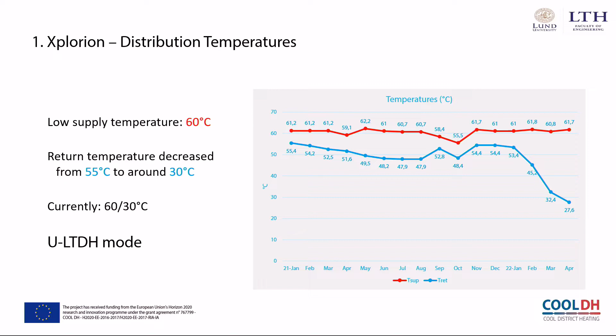So there was a problem in the system, and it was detected that there was some bad adjustment of the return domestic hot water. So the problem was detected and fixed. After that, from January of this year, the return temperature of the flats started to decrease, from, for example, 53 to 45 in February, then 32 in March, and finally in April it decreased below 30.